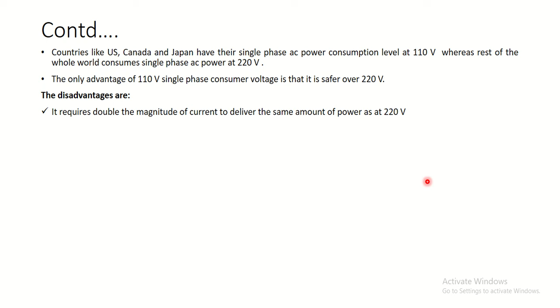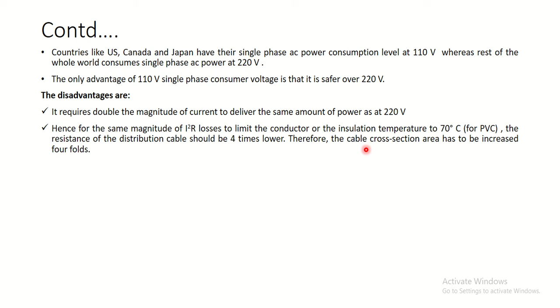So if the voltage is half, okay, instead of 220 volts we are using 110 volts, then the current is going to become twice of that. If the current is twice, then we are going to have a large cross-sectional area of the conductor. If the cross-sectional area of the conductor increases, then the temperature rise should be more, and we want more insulation for that. So there are many parameters which are going to increase, and hence, to keep the same magnitude of I square R losses and limit the conductor or the insulation temperature to 70 degrees Celsius, the resistance of the distribution cable should be 4 times lower. Okay, the resistance should be less. If the resistance is not less, then you know that the current becomes twice and it is squared, so the resistance has to be 1/4 of that. Then only the same I square R loss is going to occur in that line. Therefore the cable cross section area has to be increased 4 fold.